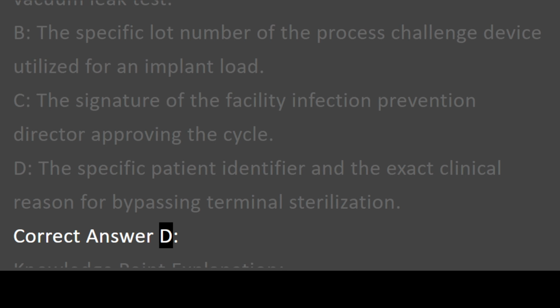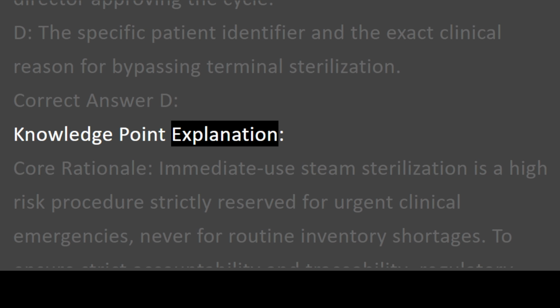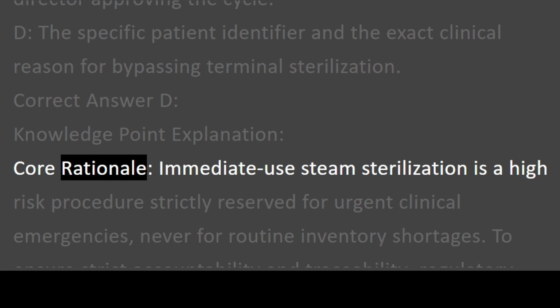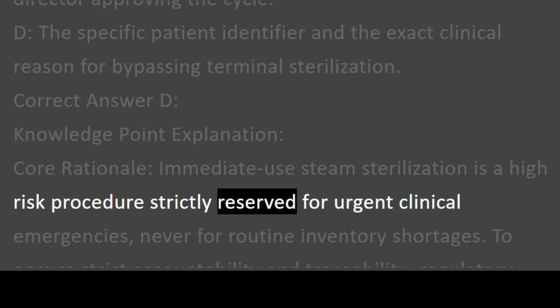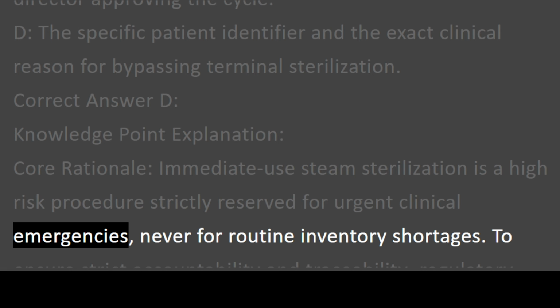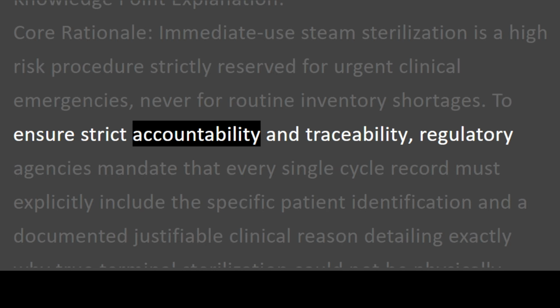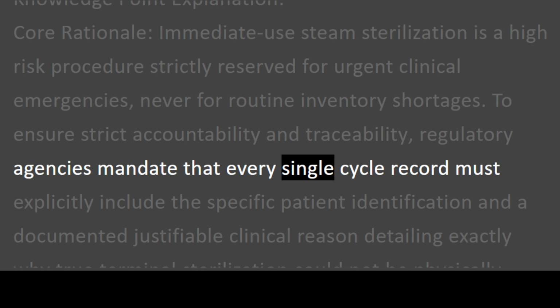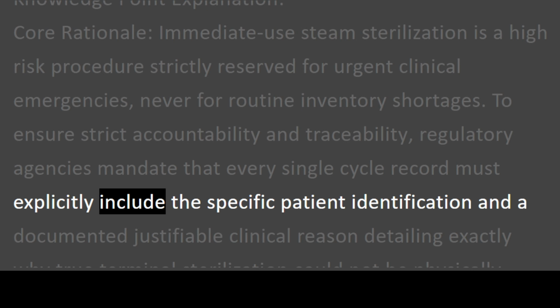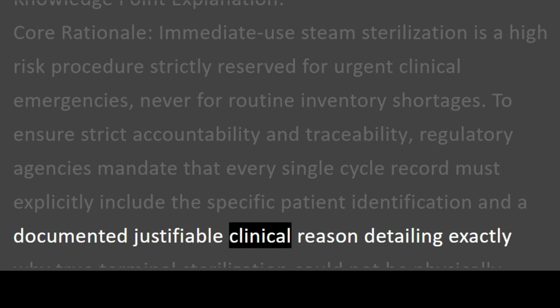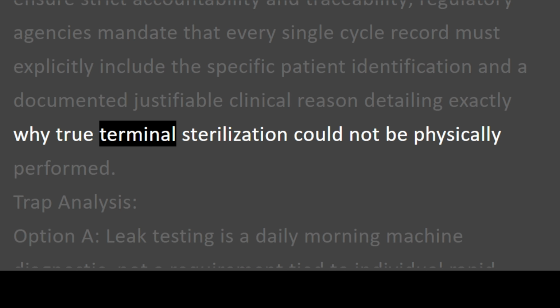Correct answer D. Knowledge point explanation. Core rationale. Immediate use steam sterilization is a high-risk procedure strictly reserved for urgent clinical emergencies, never for routine inventory shortages. To ensure strict accountability and traceability, regulatory agencies mandate that every single cycle record must explicitly include the specific patient identification and a documented justifiable clinical reason detailing exactly why true terminal sterilization could not be physically performed.